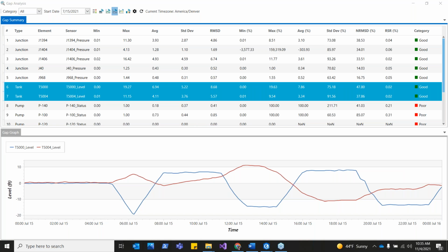And now what's happening, for the modelers looking at these tank graphs, and these aren't the actual tank time series, this is the difference in time series between tank model and measurements, but you can see they're starting to diverge as soon as the pumps kick in. And so it indicates to us that there's something probably off with the pumps. As a modeler, you might start to ask, where do I want to start, and which pump do I want to look at?